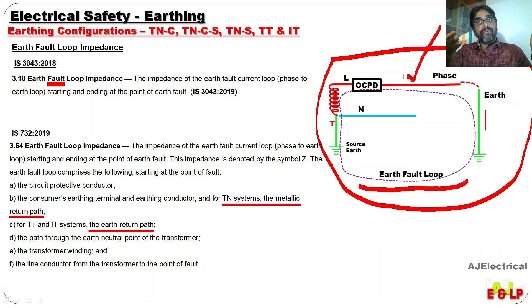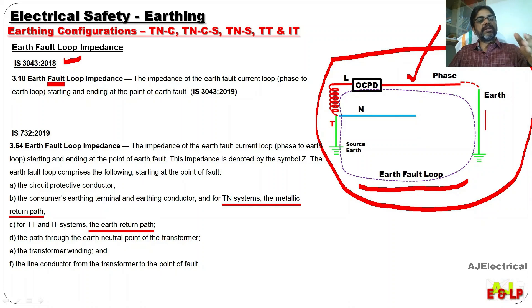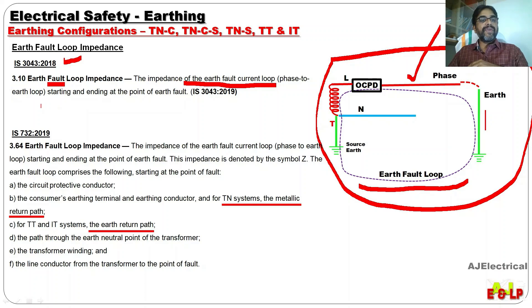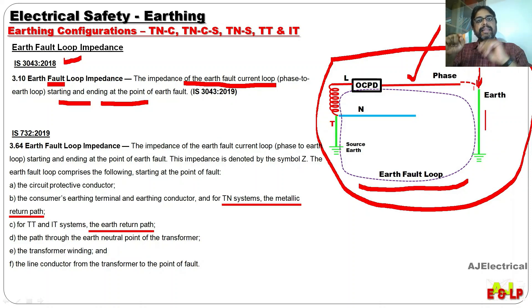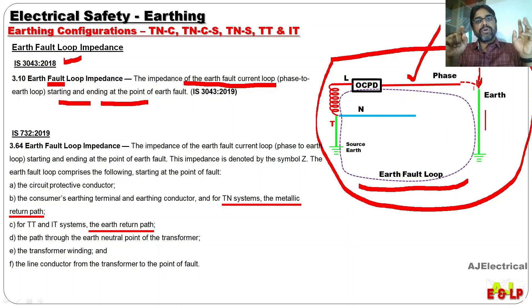If the fault current is high, the OCPD will trip faster. As per IS 3043, the Earth fault loop impedance is the impedance of the Earth fault current loop, or we call it the phase-to-Earth loop, starting and ending at the point of Earth fault. The starting and ending at the Earth fault point gives us a loop, and the impedance of that loop is called Earth fault loop impedance.